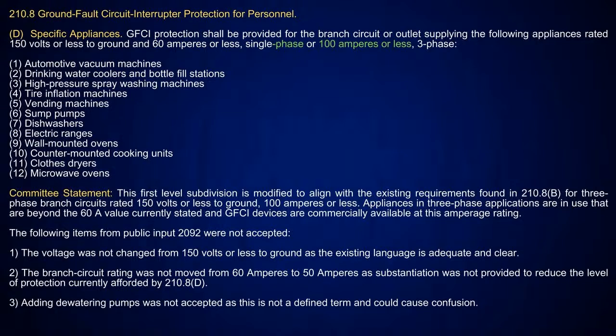Here's our substantiation, and I'll explain and prove some things. The first level subdivision is modified to align with existing requirements found in 210.8, for the 3-phase branch circuit at 100 amperes or less. It then says appliances in 3-phase applications are in use that are beyond the 60 amp value currently stated, and GFCI devices are commercially available at this ampere rating.